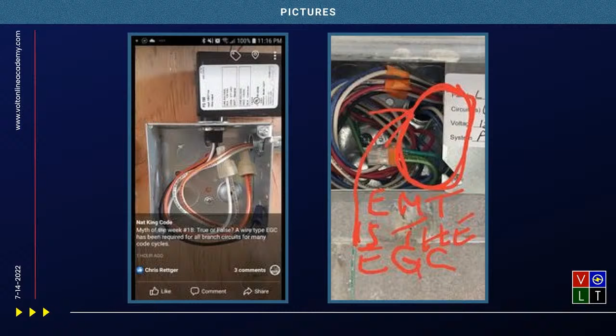But then I have to find a place to tap that wire-type grounding conductor in that relay cabinet, and there's really no space for it, no place for it to go. So that half-inch EMT comes up, hits the relay cabinet, comes out of the relay cabinet, goes and hits my junction box for the 277 volt control power that feeds this N-light device, and you're done. Piece of cake, and that's 100% code compliant. Actually, putting a ground wire in there causes more problems. So a lot of people would look at that as exceeding code.